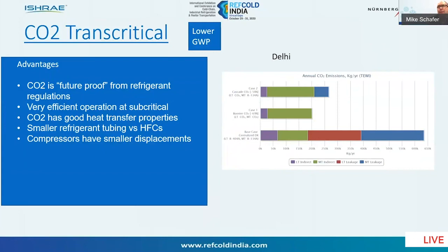So we look at the CO2 emissions for that simple example of a deli. The DX case obviously is very pronounced due to the direct and indirect leakage, and then also the calculation, and then in terms of the booster, it looks the best because there's only the indirect effect. And then the cascade has a slight direct effect due to the 134A leaking at a 15% rate.